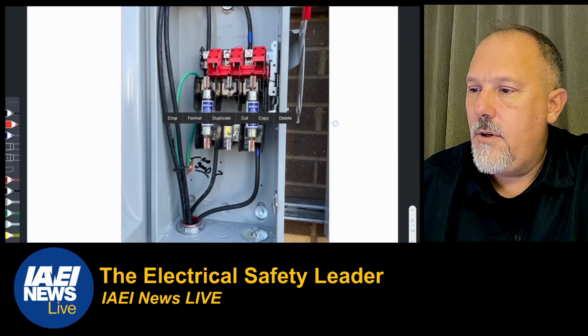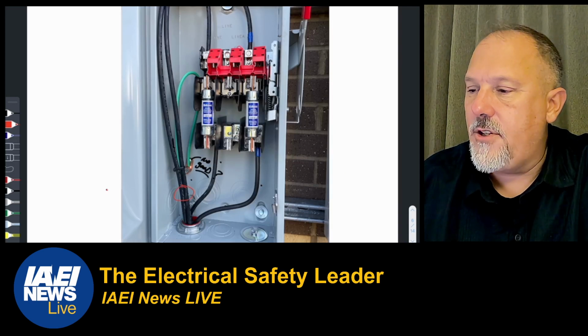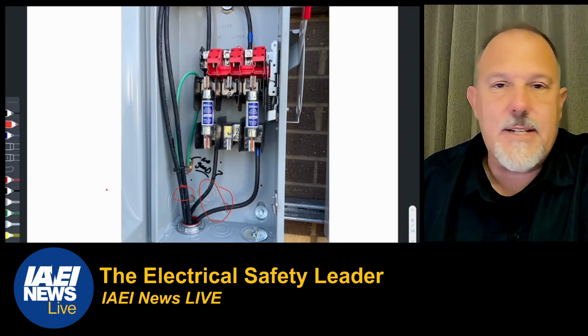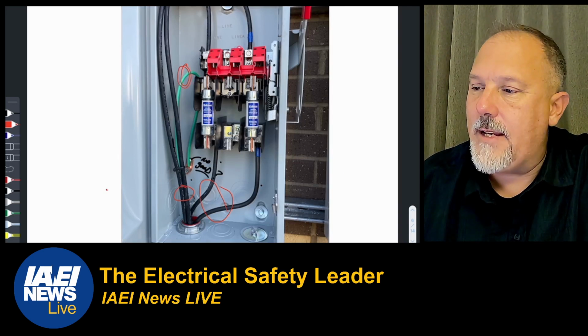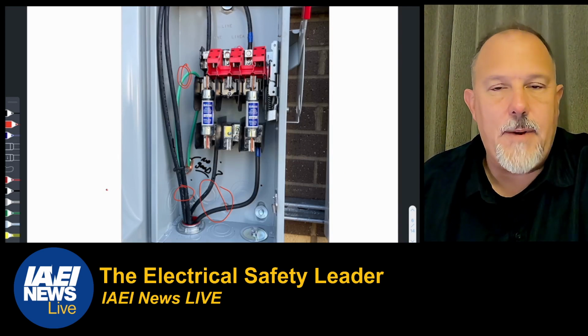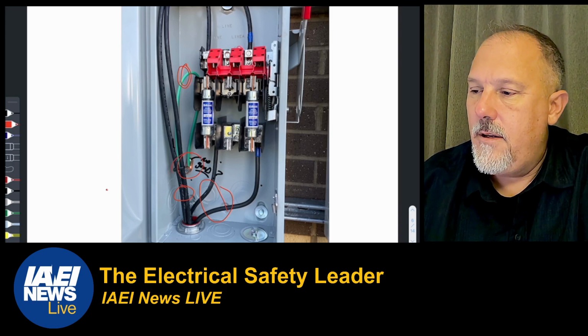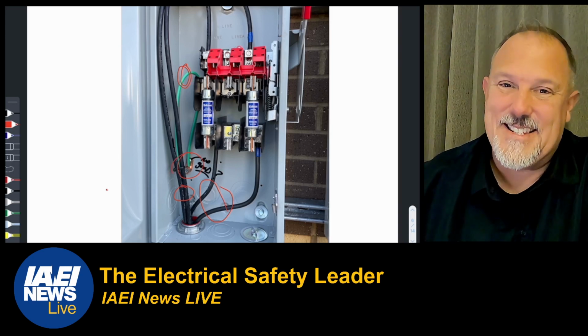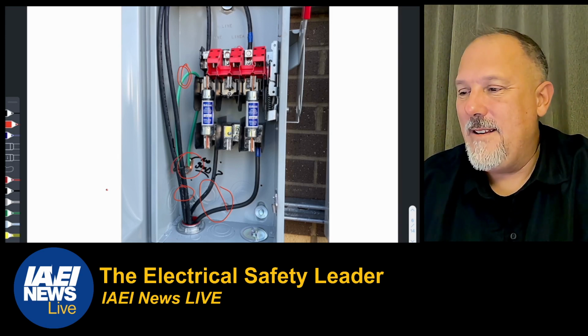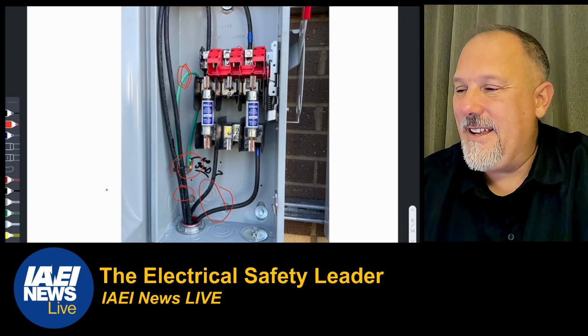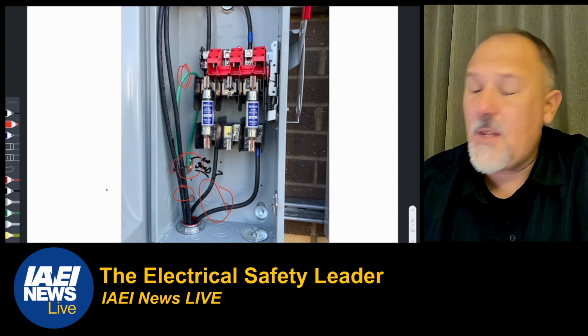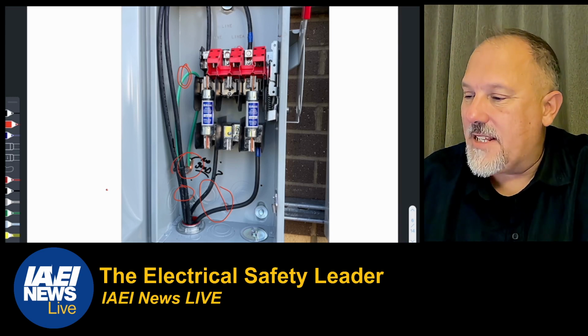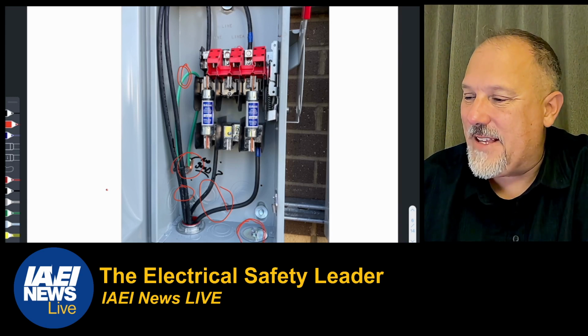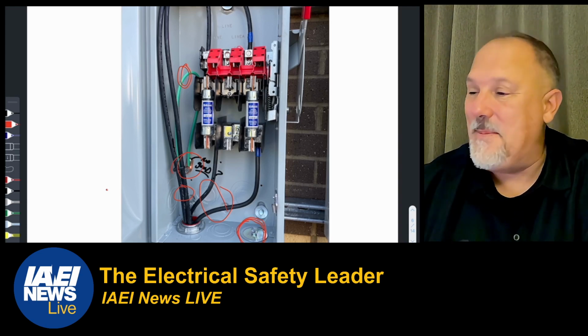You'll notice there are two hots in here. Two hots going in, two hots coming out. There's an equipment grounding conductor pulled up through the raceway and bonding through this, what we think is a tap screw, a self-tapping screw, which would be illegal. And you'll notice they plugged the holes. They had a conduit there. They plugged that hole. So good job, right?